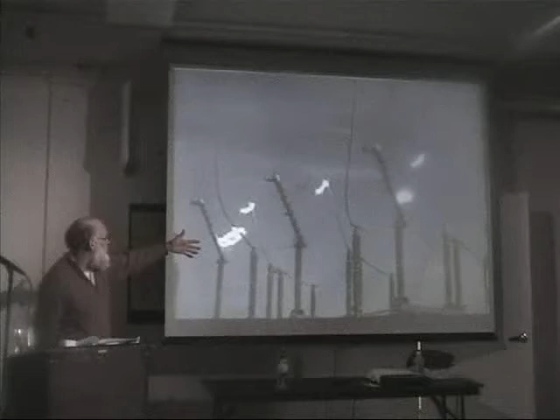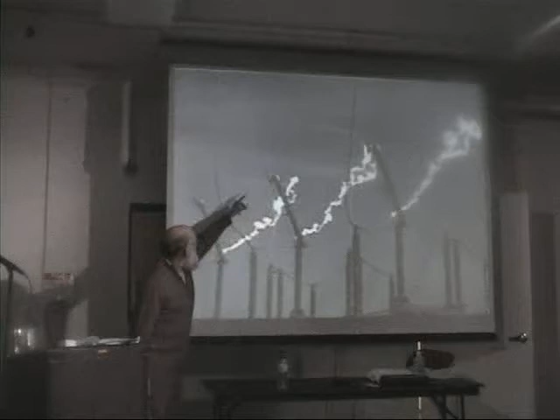Normally when the switch opens, the remaining fire is dissipated in these opening arms. As you see going through the video, it goes step by step. These were live pictures, but they're stunning to watch move. So you can see now the arcs have come off the switch and now found their way back to the line terminals.